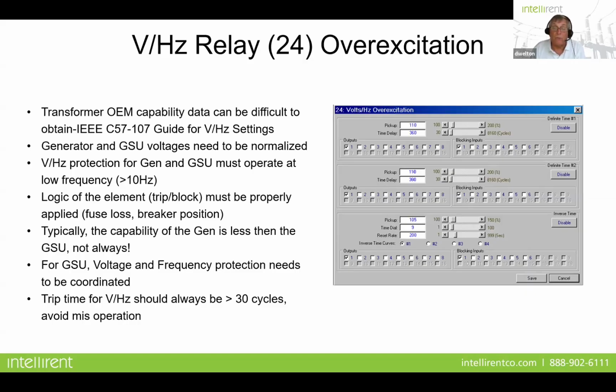And for the GSU, voltage and frequency protection also needs to be coordinated, because you want to make sure that your voltage and frequency elements are properly set, but they should be outside the setting of the volts per hertz element. And also your volts per hertz setting should be greater than 30 cycles. I'd say 30 cycles is probably the minimum to avoid a misoperation. The other thing, and this is important, since volts per hertz protection has to protect the transformer and the generator while the generator is coming up to speed, it has to operate down to 10 hertz. So anywhere between 10 and 60 hertz, that has to be enabled, because the voltage and the frequency need to be proportional as that generator is coming up to speed.